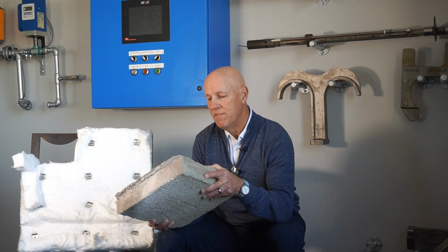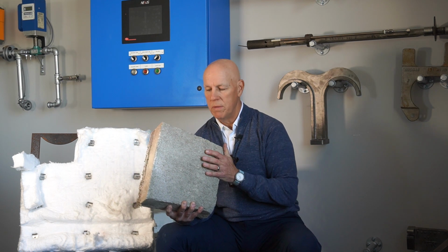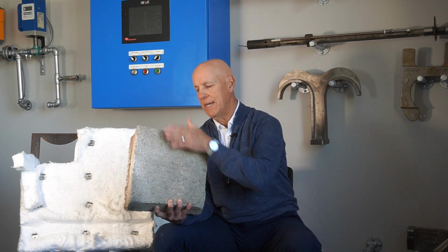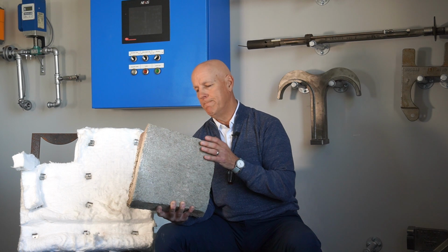One is I can have flue gas velocities along the face of this really, really high. I'm never going to shred this, rip it up. I can put gases along the face of this at 150 feet a second, and it's happy. Nothing happens to it. If I design a heater or if I fire a burner really hard and I have gas 150 feet a second across this, it's going to shred it.